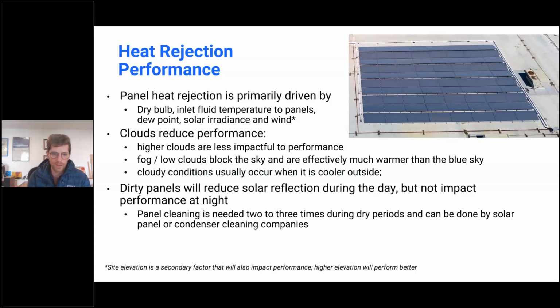This is a renewable technology. Clouds will influence the performance. Higher clouds tend to be colder, and so they don't impact performance as much because they're still cold, just like the sky. The hardest operating conditions would be low fog, and so Seattle, Washington wouldn't be the first place I would want to do a deployment, just because the fog is really low. It's typically warmer than high clouds or even the blue sky, and so that reduces the performance by as much as 40 or 50%. And then the other thing to acknowledge is usually when it's cloudy outside, cooling loads are lower, and so in general the air is cooler, and so you can balance some of the heat rejection. Instead of radiation, it goes by convection to the local atmosphere. But we don't tend to see too much of a performance variation with panel systems in most locations.